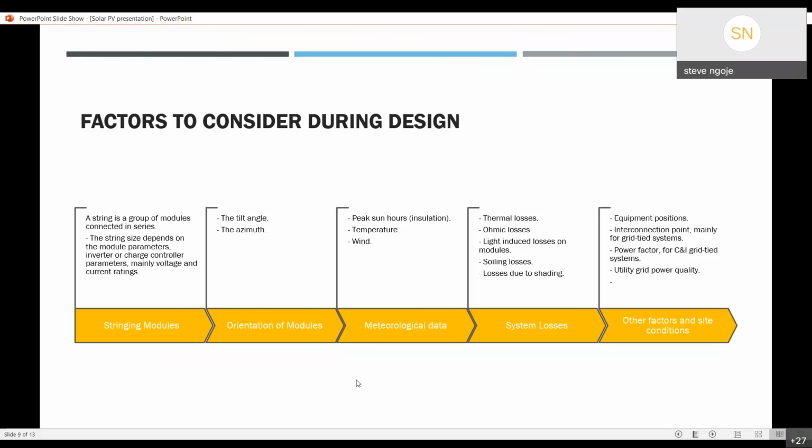For if you are doing your module installation on a mabati roof, then you've reduced that distance, the clearance underneath, so the wind flow is not going to be that great. That is when we consider using a factor like 20. For 15 on PVCs that you use when the backside of your module is in direct contact with the surface, in that there is no room for wind to flow or anything to flow underneath it. So it's going to have worse thermal losses. That's something that you need to factor in during a design.